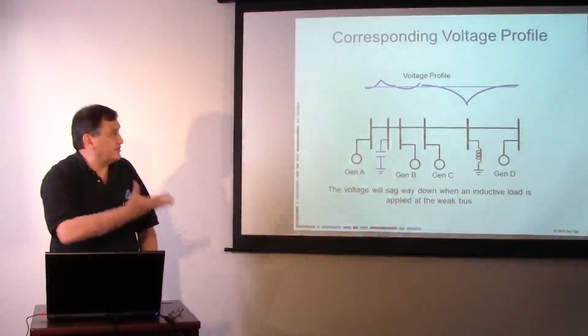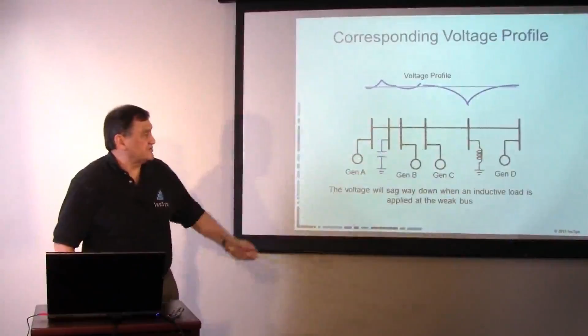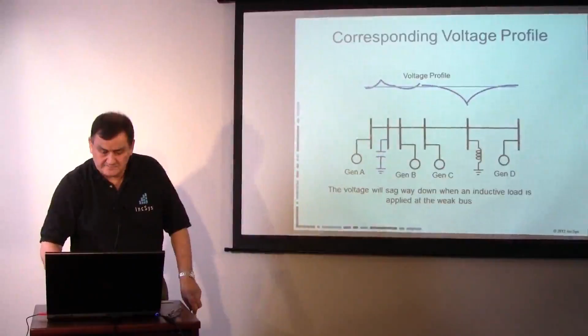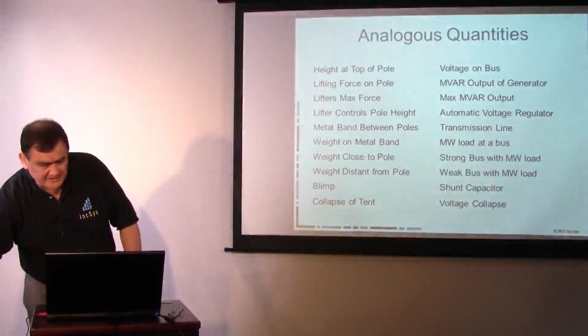So in the case with the reactor, our voltage profile is analogous to applying the weights. Again, our generators are nailing the voltage at the set point, but the reactor drags down the voltage and lowers it below the nominal value. So if we go through the comparison, the height of the top of that pole from the lifter is the voltage on that bus. Your generators, the lifters, are like generators. They are ideally anchoring the voltage profile throughout the system.